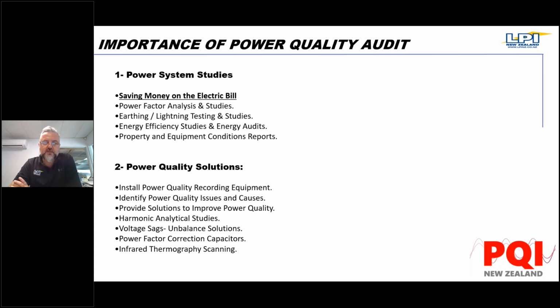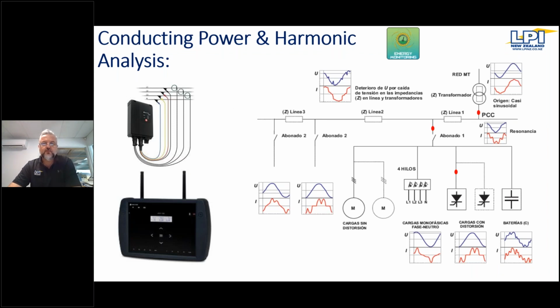The harmonic issues with the chargers are that they generally produce about 30% harmonic distortion, and as I mentioned, it is quite important to address these things. These are some of the services that we can offer, but whichever way you decide to go, it is always advisable to do a power audit to find out exactly what the situation at your facility is. Which means that you should do energy efficiency studies and power factor and harmonic studies, and then find out who can provide the report for you and assess the whole situation. There are a number of different ways that you can conduct the power analysis, including the harmonic analysis, either by fixed power analyzers or portable power analyzers.